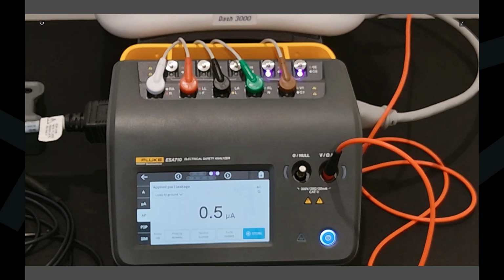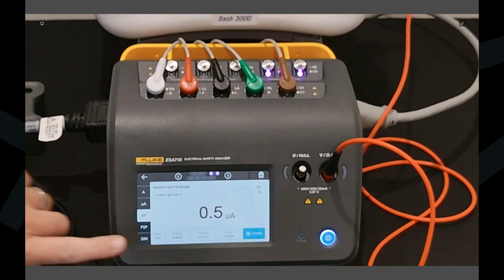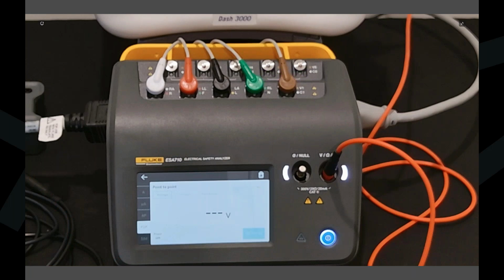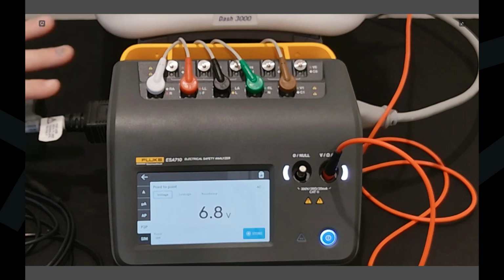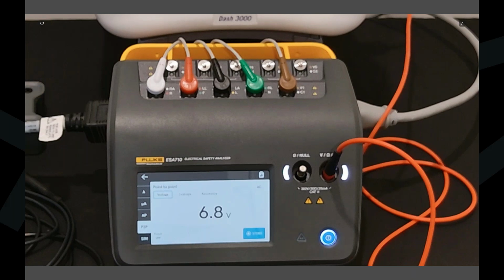Now, point to point - we've gotten a lot of feedback from our imaging team. Hopefully there are some of our imaging FSEs out there, and we hear you on some of the challenges of doing point-to-point testing when it comes to imaging. A lot of what we hear is, you can't get this instrument into the MRI suite. While this one is not compatible to go into your MRI suite, what we have is 75-foot leads. Here we just have some small ones, standard leads and accessories.